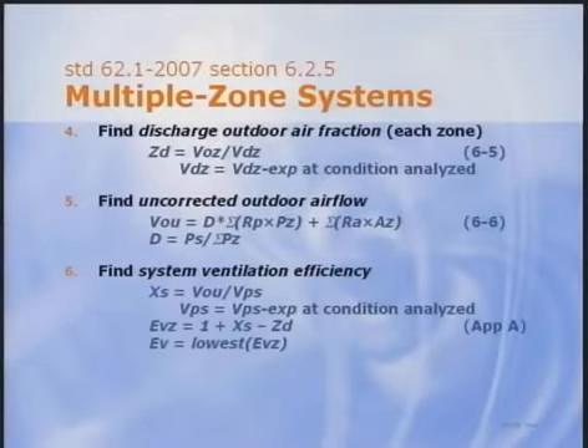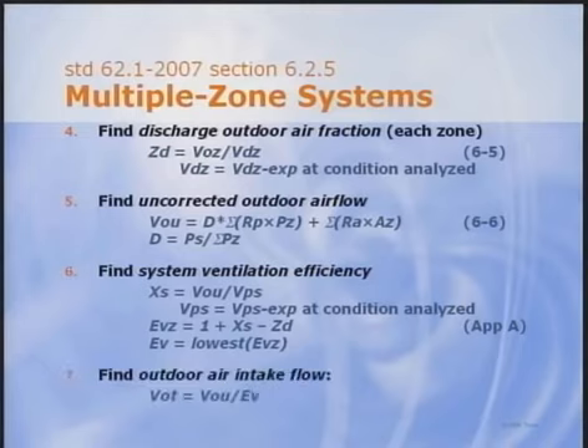The 6th step is to find the system ventilation efficiency. To do this, first find the average outdoor air fraction for the system. It's the ratio of uncorrected outdoor airflow to the highest expected system airflow at the condition being analyzed, which is probably block airflow for conservative designers. Next, find the ventilation efficiency for each zone, and then the system ventilation efficiency, which is simply the lowest of all the zone efficiencies. The 7th step is to divide the uncorrected outdoor airflow by the system ventilation efficiency to find outdoor air intake flow required. That was pretty quick, but if you want more details about ventilation calculations, we did a broadcast and wrote some newsletters and some journal articles about it, so the bibliography includes plenty of resources.